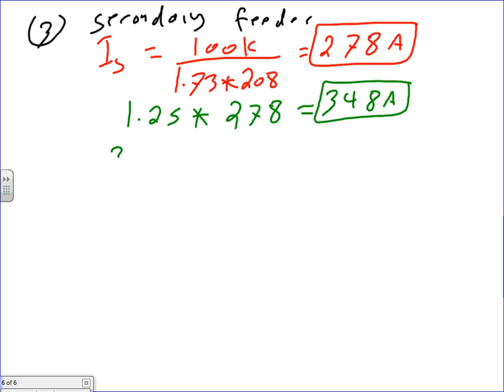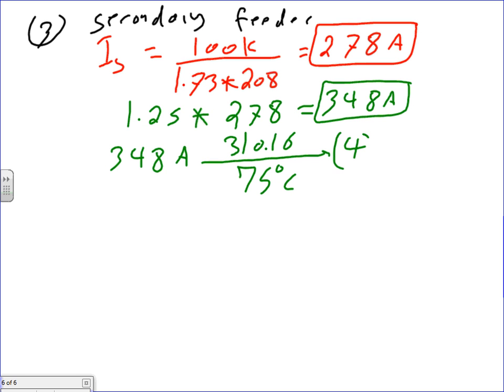Now 348 amps. Take this one to Table 310.16 under which column and why? 75 column over 100. And let's carry this with one feeder. That will give me how many conductors? Full neutral. I'm going to carry full neutral. How many conductors and what size? 500 kcmil, 4 of them. So 4 conductors, 500 kcmil.